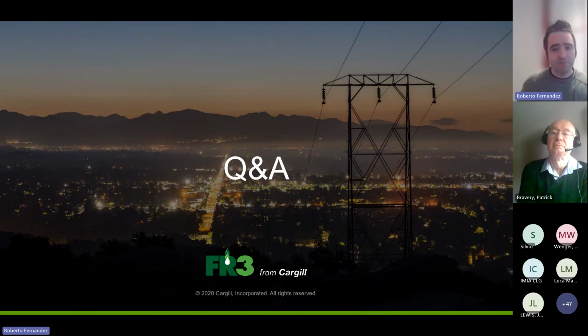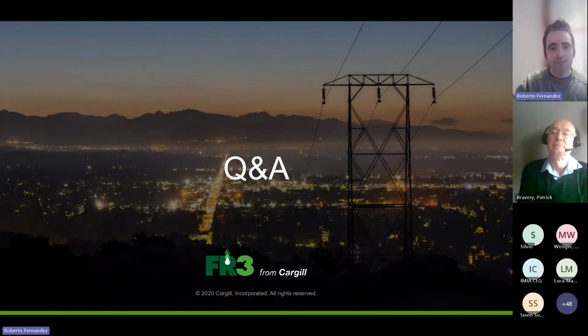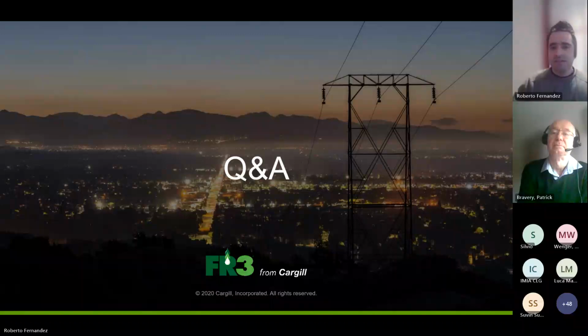So FM firstly qualifies fluids, and it's an approved fluid based on FM. The fluid is subjected to a series of tests. And then there is a second step, that is a transformer that is FM approved, that involves additional protection requirements connected with the transformer itself. So one of the conditions, of course, is to have a fluid inside that is FM approved, but the transformer itself needs to comply with additional requirements. I don't know if I have answered the question.